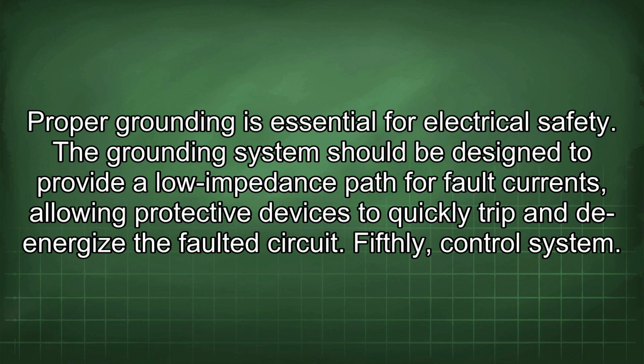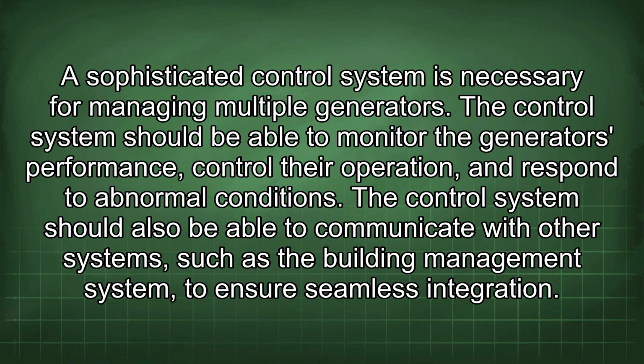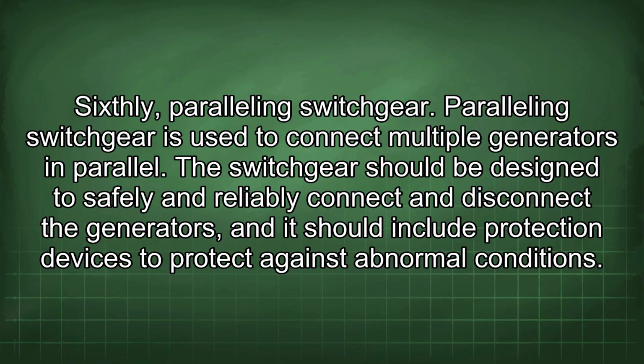Fifthly, control system. A sophisticated control system is necessary for managing multiple generators. The control system should be able to monitor the generator's performance, control their operation, and respond to abnormal conditions. The control system should also be able to communicate with other systems, such as the building management system, to ensure seamless integration. Sixthly, paralleling switchgear. Paralleling switchgear is used to connect multiple generators in parallel. The switchgear should be designed to safely and reliably connect and disconnect the generators, and it should include protection devices to protect against abnormal conditions.